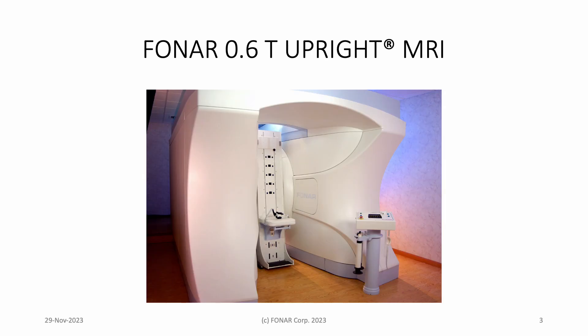The upright MRI may be unfamiliar to many of you. The patient support moves with three degrees of freedom between the planar surfaces of a non-superconducting dipole electromagnet that has a horizontal 0.6 tesla magnetic field oriented transverse to the patient.